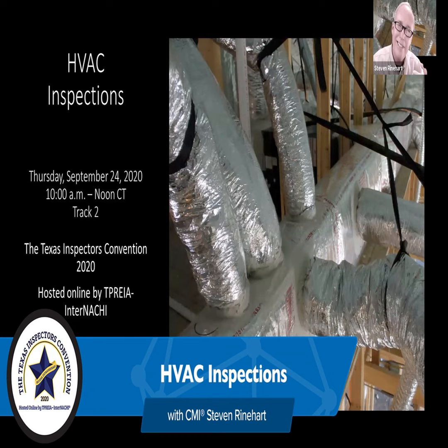So you have this scenario where you run your primary condensate into the bathroom sink, which if it gets clogged up, the unit does not stop making condensation, and maybe you're not there to notice that it's filling the bathroom sink, overflowing, and there's no place to go but the floor.